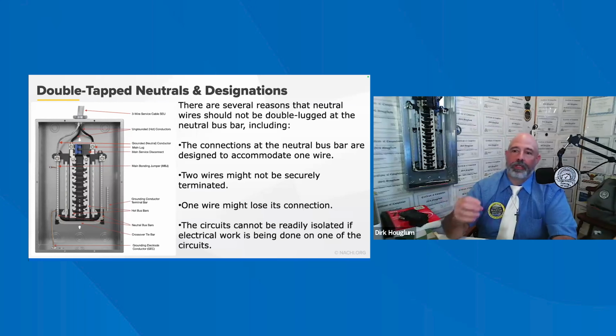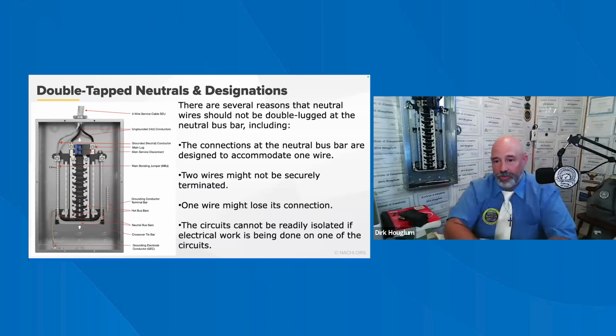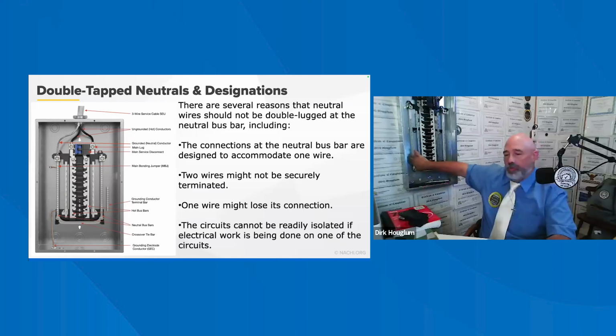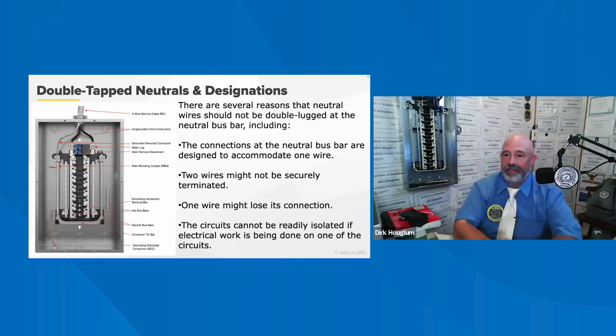It is sometimes said that double lug neutrals were not prohibited by the National Electrical Code until 2002. This is an incorrect interpretation of the NEC. Until 2002, the NEC simply stated that panel boards must be installed according to the listing by Underwriters Laboratories. So whoever designed the panel said, oh yes, you can put two in there. Well, the NEC never allowed double tapping or double lugging of neutrals, but it wasn't addressed until 2002. Wires in the panel must be correctly designated for their use.